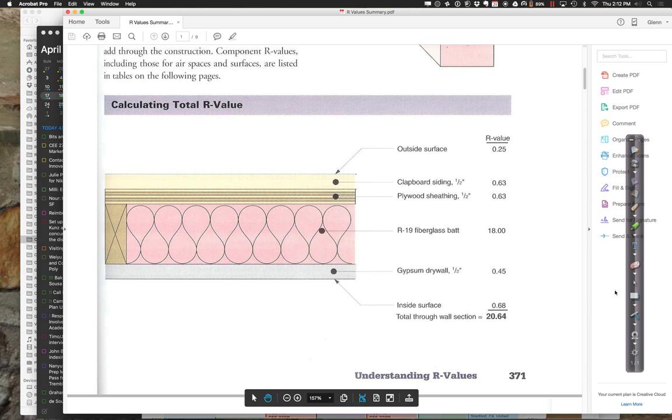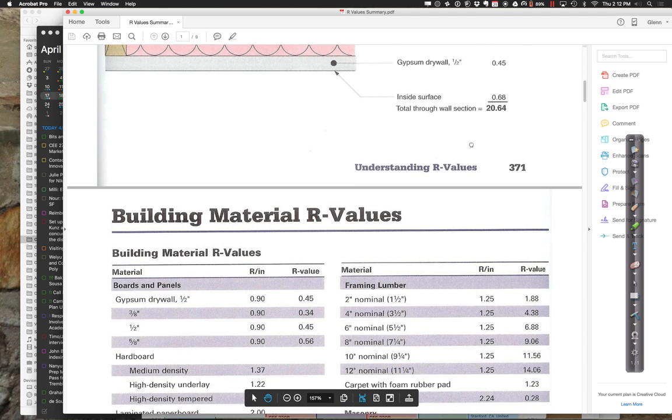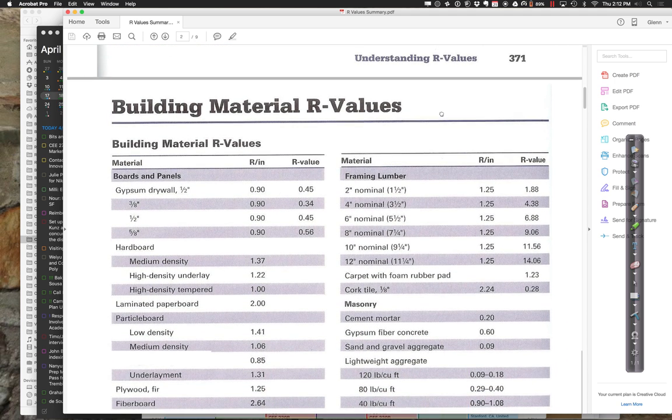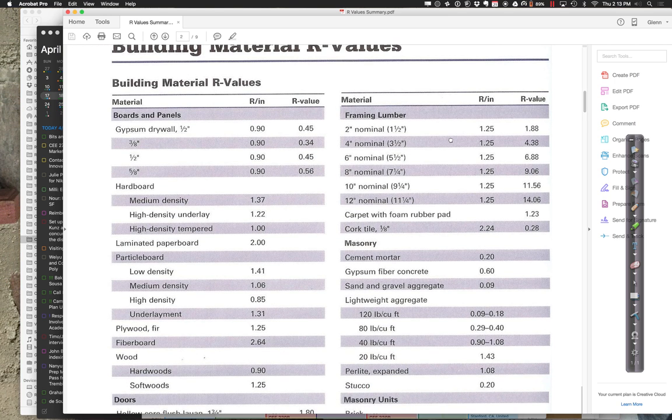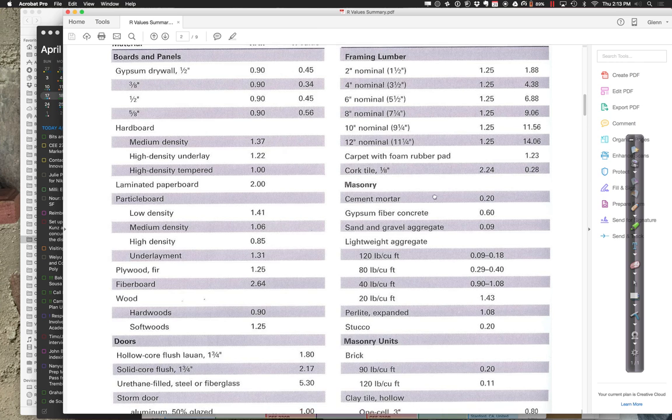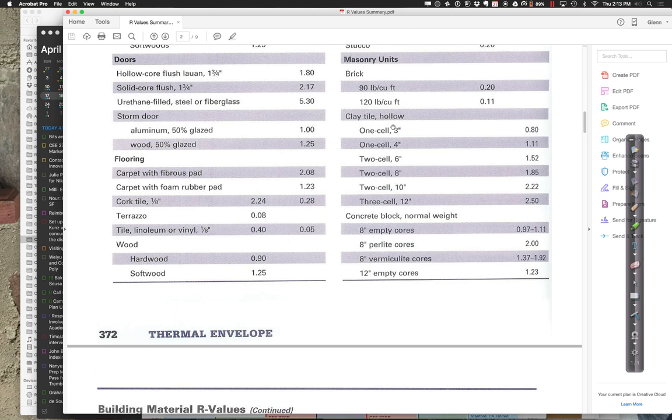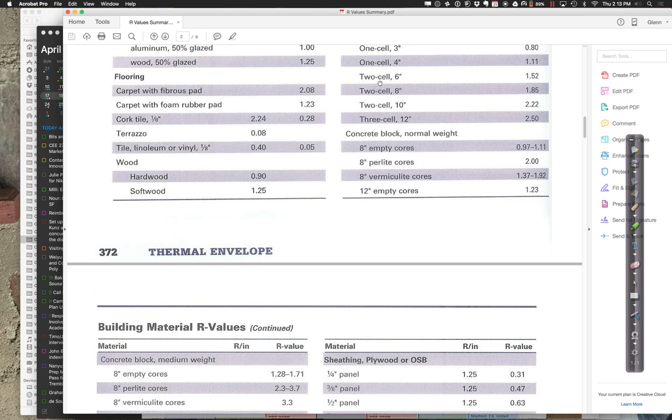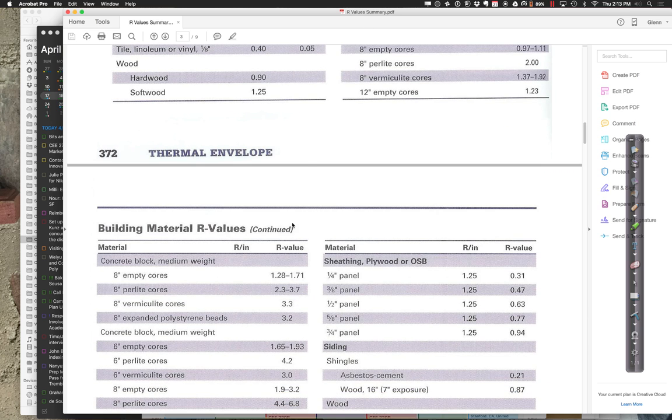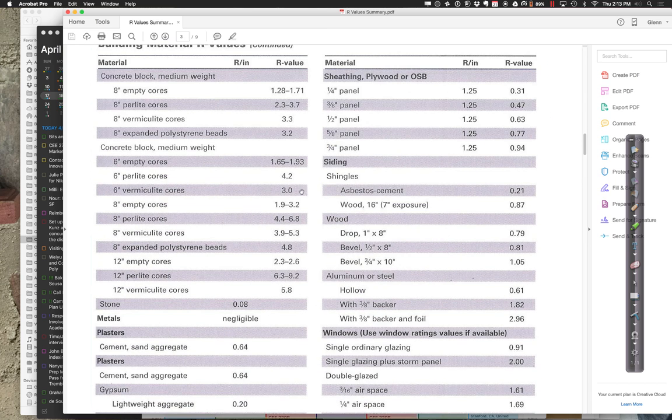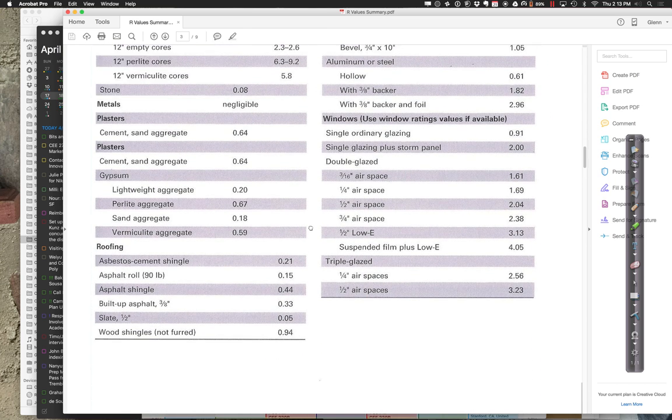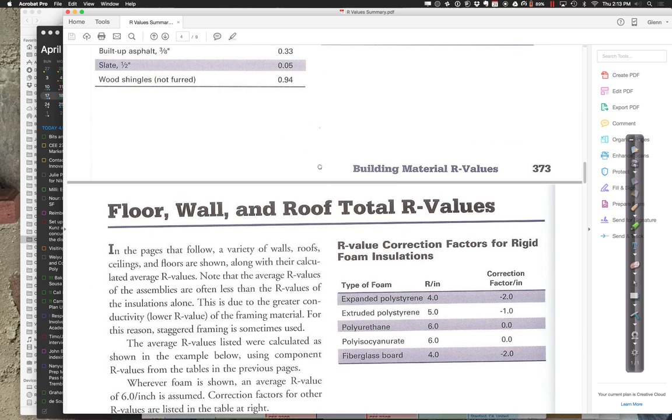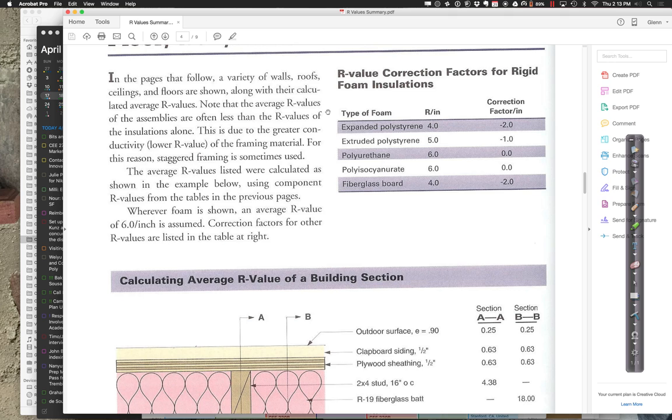If I come zipping on down here, let's see what I got. Gypsum, hardboard, framing, lumber, fiberboard, doors, masonry unit, flooring, concrete blocks. You'll find out concrete is actually a very bad insulator. Here we have some values. Polyisocyanurate, I love that word, has an R value of about 6 per inch.